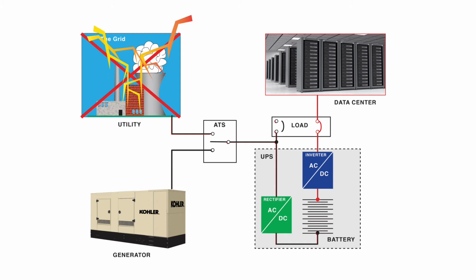When the utility goes offline, the UPS, such as a battery, rectifier and inverter system, provides uninterrupted power to the data center load while the generator runs up to speed. The set runs up to speed to take the full load. When the utility comes back online to take the load, the generator returns to standby mode.